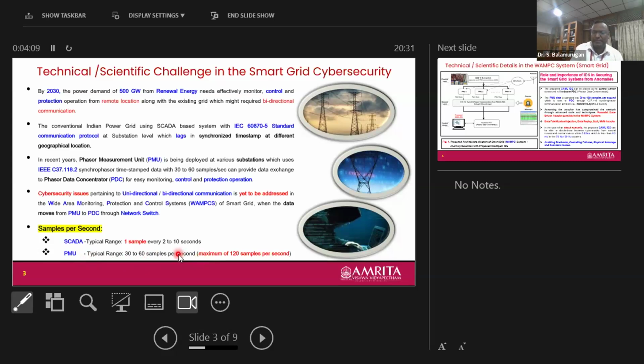So why is this sampling rate required? We need to detect whether any anomaly has happened in the critical systems. We can't rely on one sample per second every 2 to 10 seconds. As per the Nyquist theorem, we require at least 120 samples per second to detect the anomaly. This is a cyber security issue pertaining not only in India but all over the world, where bidirectional or even unidirectional communication can create issues in the wide area monitoring, protection, and control system. This problem should be addressed through machine learning techniques.